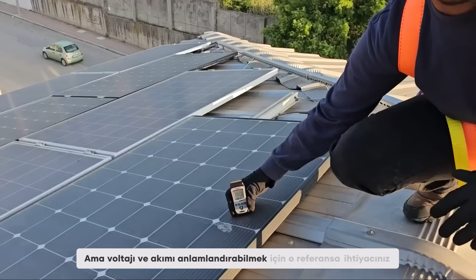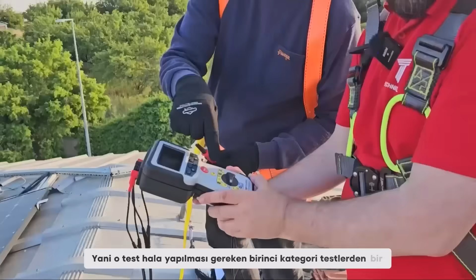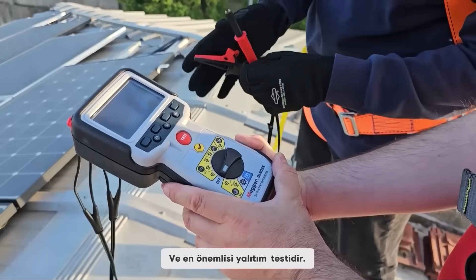And then still in category 1, we go back to the continuity or the bonding resistance of the grounding. This is a joker device, we can say. So that test is one of the category 1 tests that has to be done. And then the big one is the insulation test. So this is the MIT2500. This one can measure insulation resistance with voltages up to 2,500 volts. At the moment, this is the smallest 2.5 kV insulation tester in the world, with all the regular safety features that we have as standard in Megger.